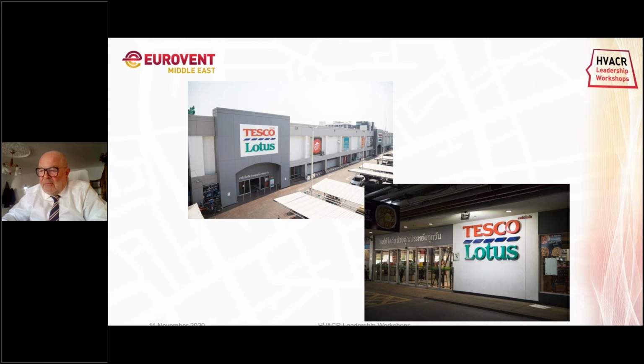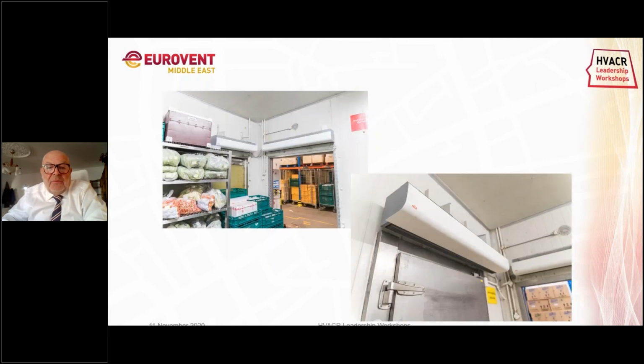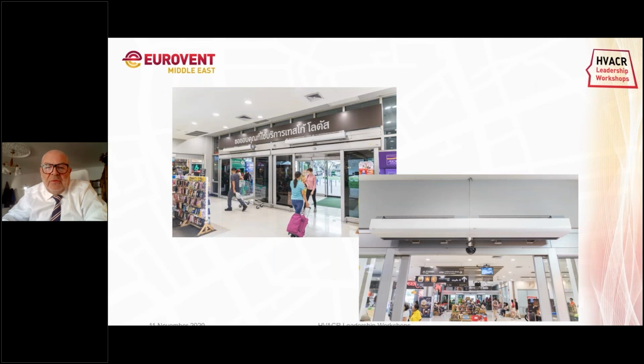So one of the case studies we've done, we did at the Tesco premises in their supermarkets and in their cold storage. It turned out very well, so now they are replacing all their plastic strips in the cold storage with air curtains because they saw a payback time of less than 2 years. They also continued with the supermarkets and installed their air curtains for the entrances.